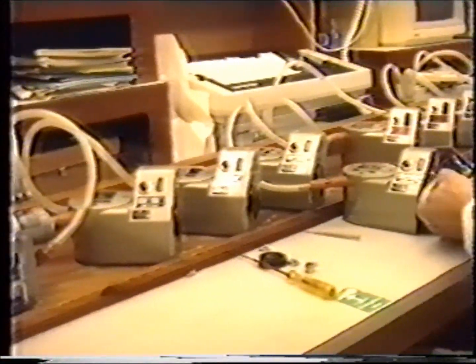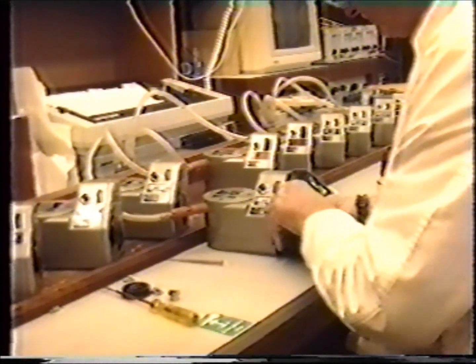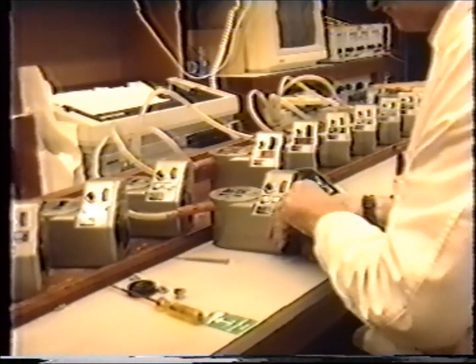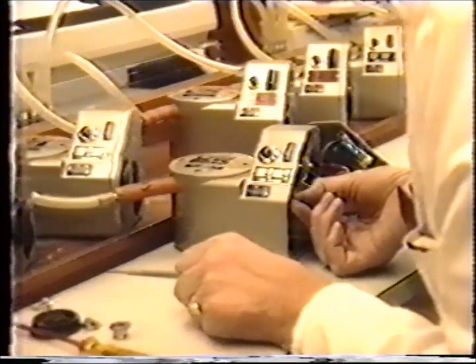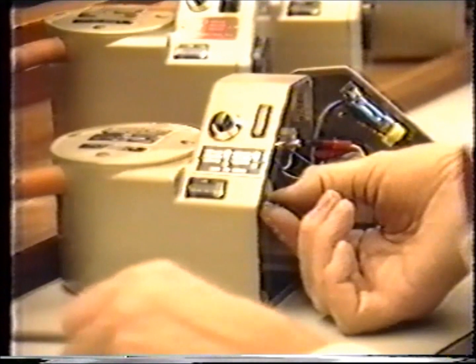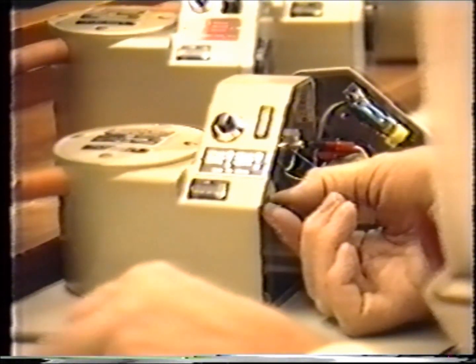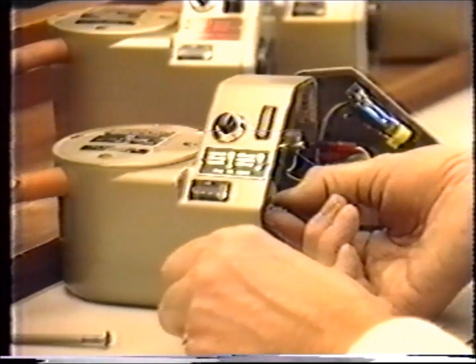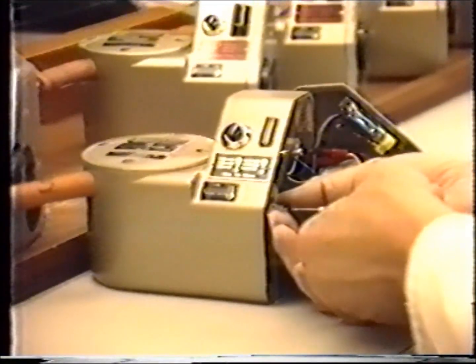Precision aneroid barometers are the bread and butter of the Quality Assurance Lab, with nearly 1,000 calibrated each year. These instruments are used extensively throughout the armed forces, but their most important role is that of station barometer at the many Met Office airfield locations. Aircraft altimeters are set on barometer readings, and therefore accuracy and reliability are paramount.